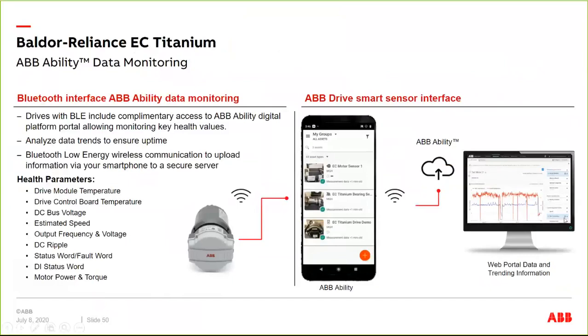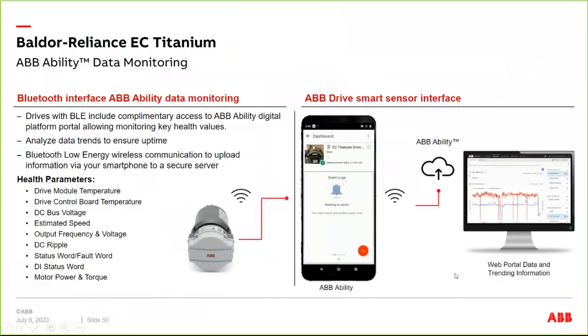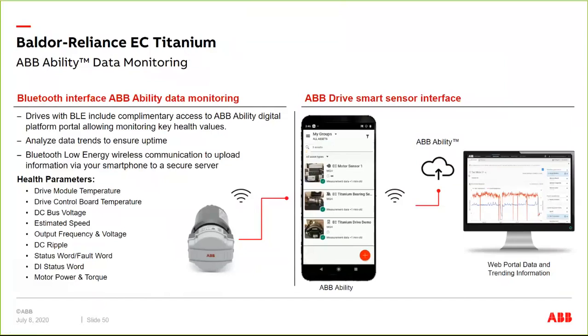Again, you plug in, this is the ABB Ability app. Basically, there's no subscription, it comes standard with the drive, it's pre-provisioned, and basically you go in and you just click commission a new asset. It'll find the sensor on the drive. You just click the plus symbol, and it'll commission that as a new asset, and you're ready to run.